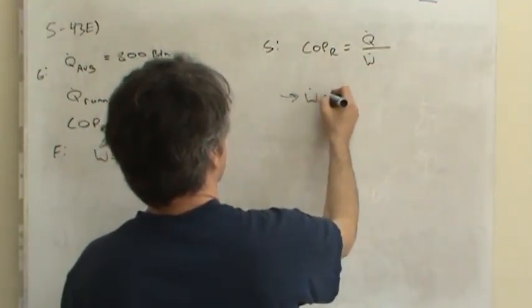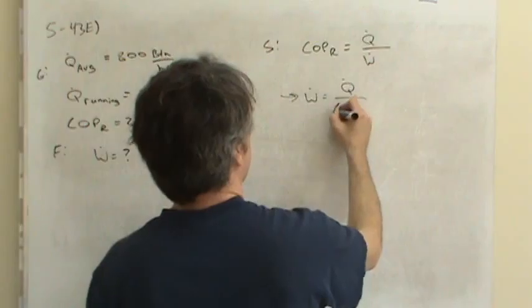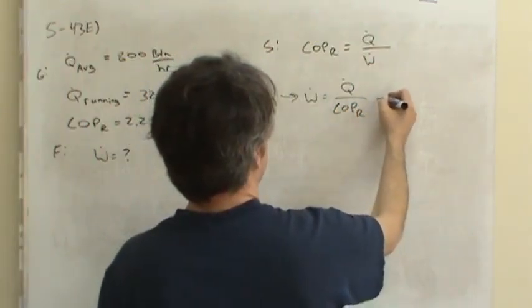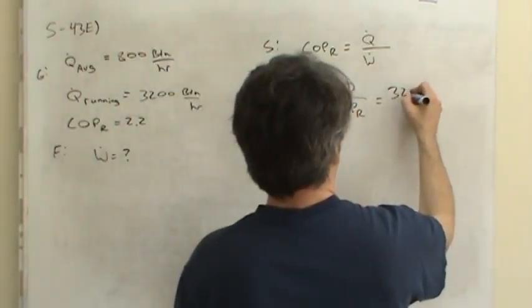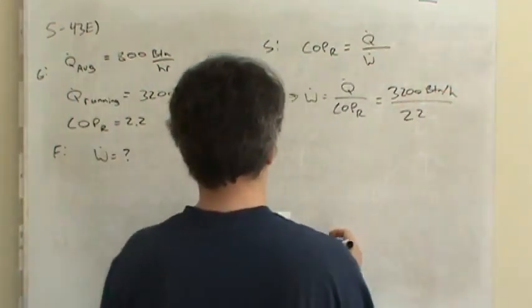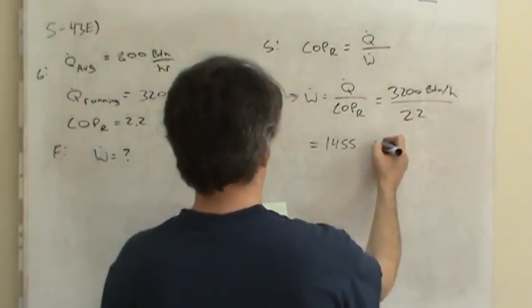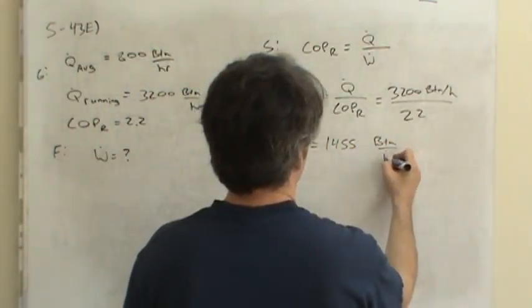So all we have to do is rearrange this to solve for the power input, and it would be the heat flow rate divided by the coefficient of performance of the refrigeration system. So that's 3,200 BTUs per hour over 2.2. When you plug that in your calculator, the power input is 1,455 BTUs per hour.